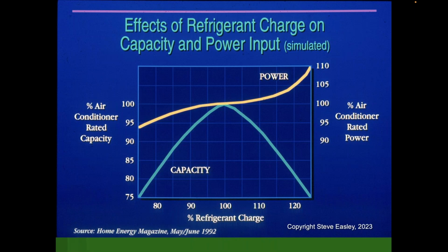We're talking about charge, the refrigerant that goes into the system. Let's say we're at 100% of charge, 100% capacity and 100% efficiency. But let's look at what happens if we're 25% undercharged. Our capacity drops by 25%, and our efficiency drops. So we paid for a 4-ton system, but we get a 3-ton system, right? And this is data we've known for 30 years.